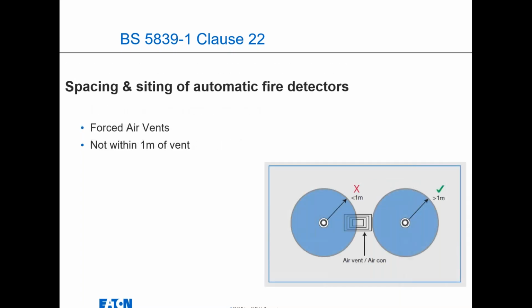When you've got forced air vents, you need to not be within a meter of those, so again you need to space your detectors accordingly. I've seen lots of installs, and I know it says that sometimes that's where it goes on a drawing. The common sense from the installer has to prevail, so they have an obligation to make sure they're not putting it within a meter of that forced air vent, because obviously if you're forcing air through that, then you're pushing smoke away from the detector and stopping it performing.